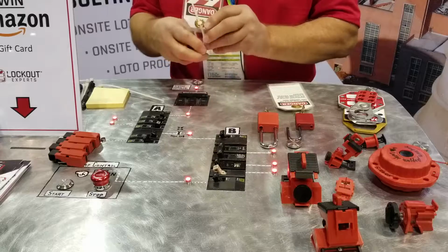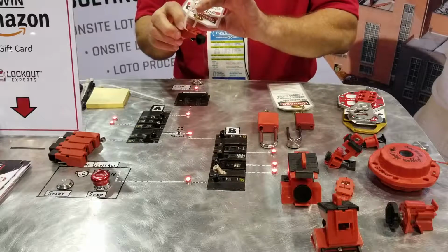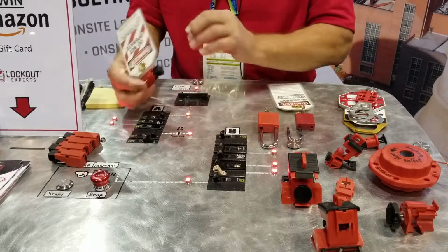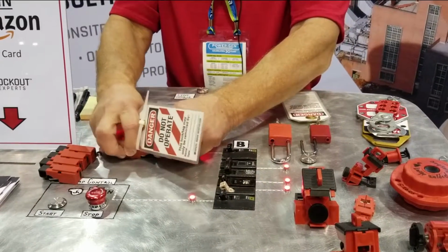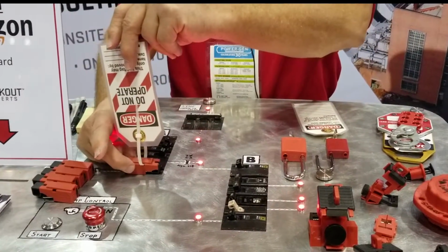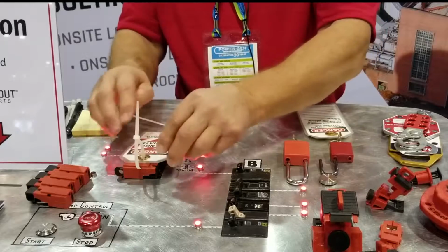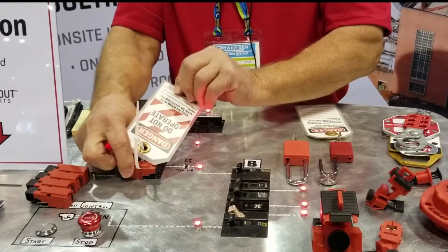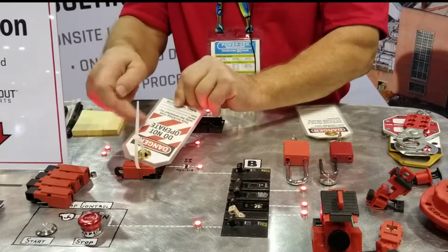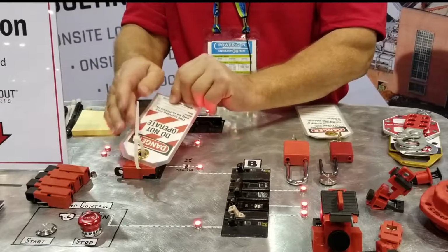Provide indication of who I am as I'm working on that device. What we've done with this is we've created a way that with the tag we can now lock the system in place. So I'll put the isolation device on top of there. You'll hear a click. This now prevents the device from being removed. It's all done with what we call a tag lock.